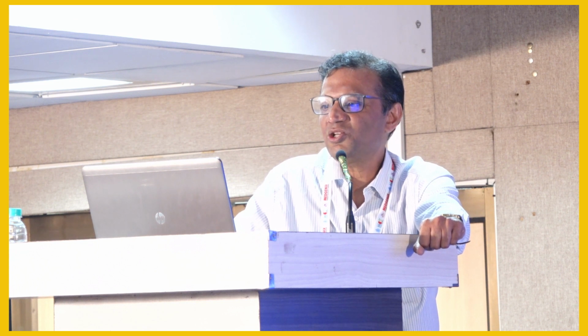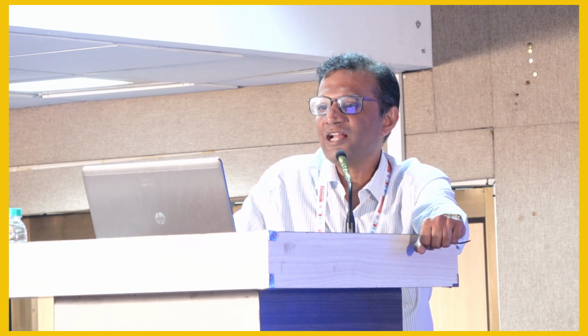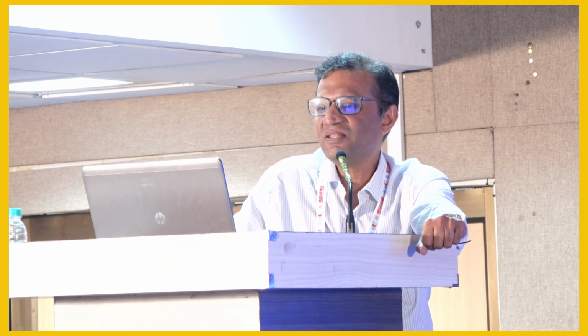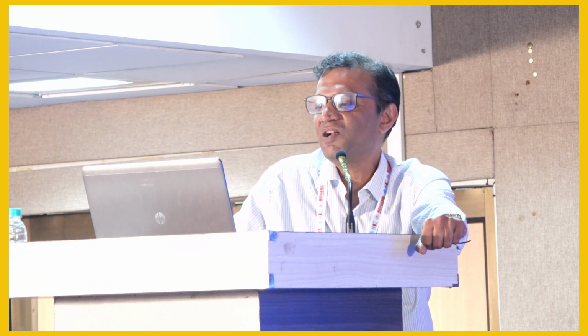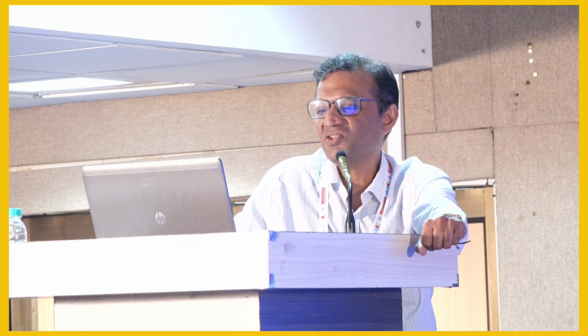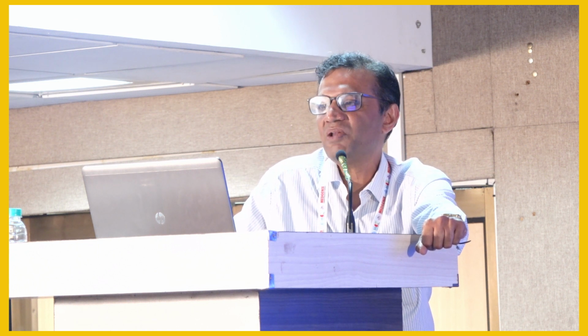In this situation here, I have shown you the actual transmembrane pressure is 0, but because of the number of sensors, the Fresenius 4008 will display the transmembrane pressure as -40, the Baxter Tina will display -60, and the Gambro will display -50, all of which are wrong, but because there's a volumetric balancing chamber, it doesn't really matter.